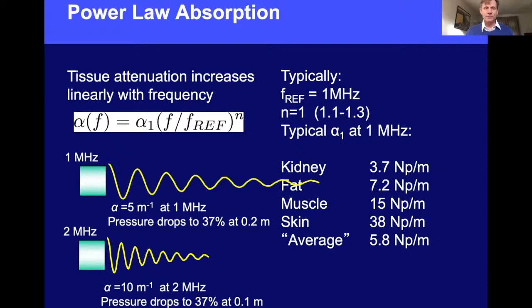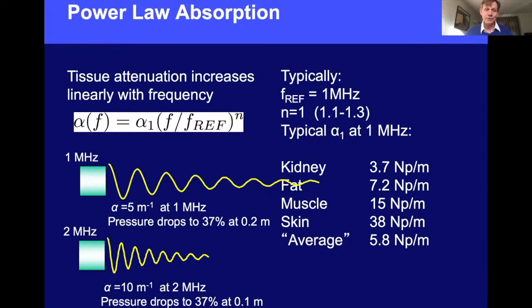Going higher in frequency means the signal decays more quickly. At one megahertz with alpha = 5 inverse meters, the pressure drops to 37% in 20 centimeters. At two megahertz, alpha doubles and pressure drops to 37% in just 10 centimeters. For imaging, this limits how far we can penetrate — high frequencies give a better image but don't allow deep penetration. In therapeutic ultrasound, the absorbed energy can be used for heating, but if all energy is absorbed before the target site, we can't get the desired therapeutic effect.